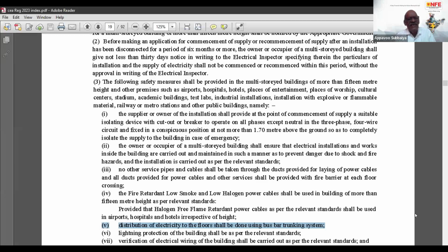These bus bar trunkings are so small. Something like 63 amps is sufficient for a household. Even a 5-bedroom sophisticated flat can have all its connections supplied by 63 amps, and that size could be about double the size of an LED tube lamp. This is not the big 1000 or 2000 amp bus bar, it's very small, only slightly higher than a cable. It doesn't have insulating materials, so toxic fumes won't come, it is only metallic. So it's a very welcoming trend.